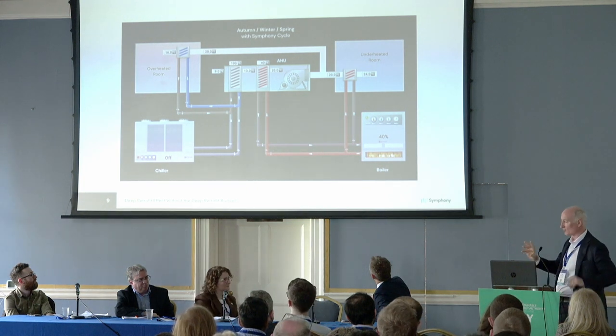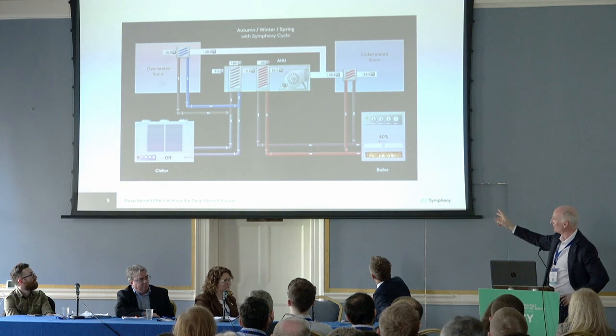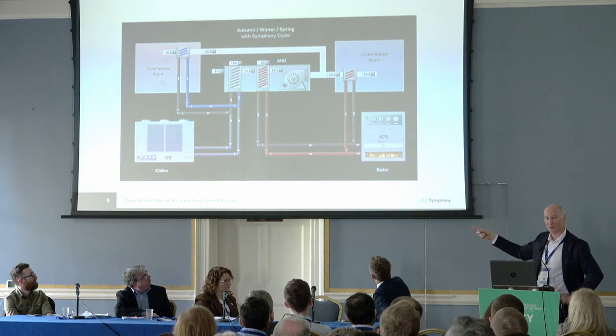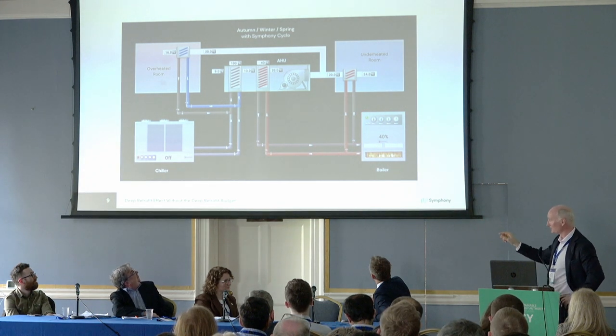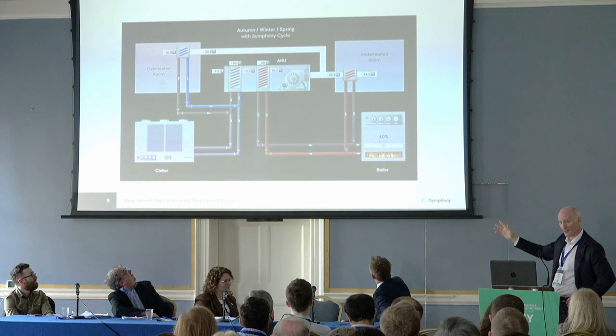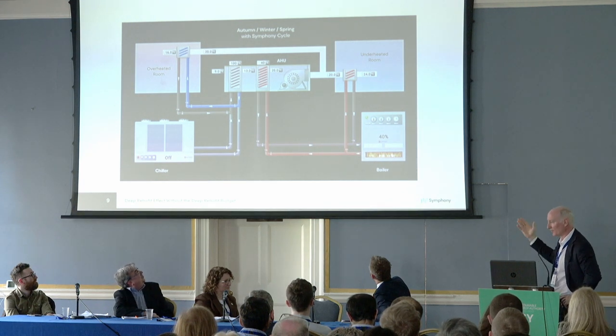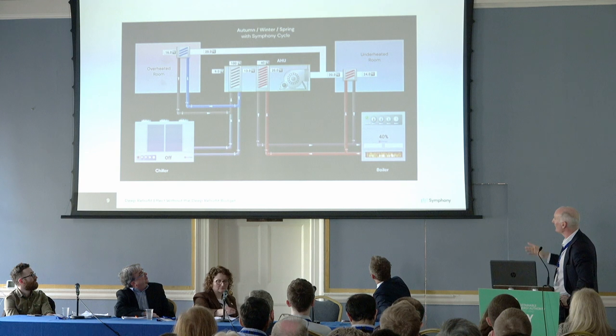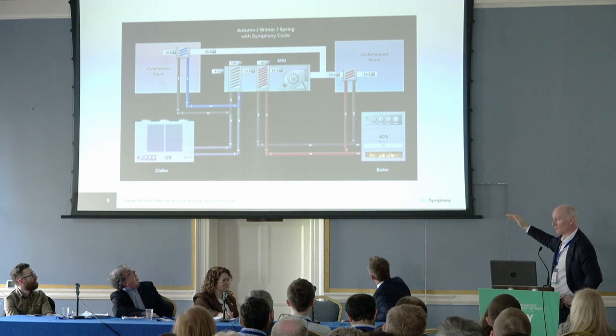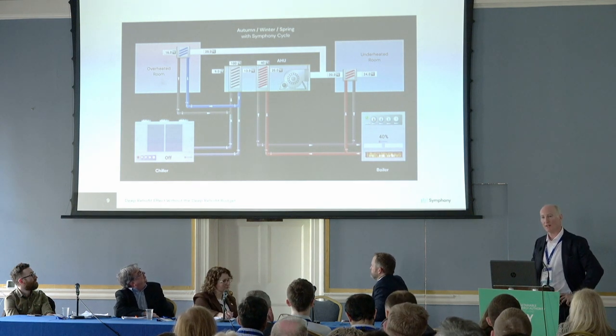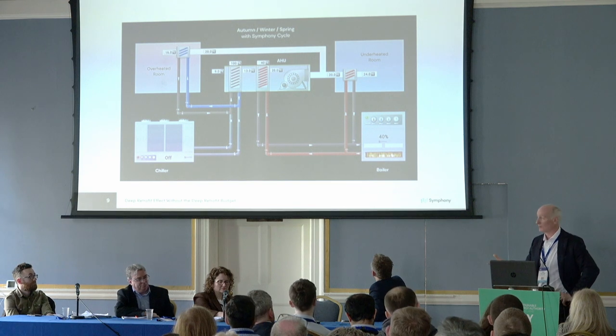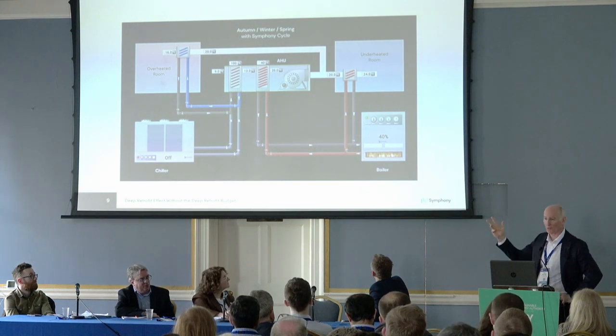Conversely, with that transfer of heat, you're putting it where you want it, it's 100% free heating, which goes into your heating system. Net effect, your chiller's off entirely, and the primary pumping, and if there's condensing pumping as well, that's off, and your boiler is stepped back or off. So it's a phenomenal process. It's got zero input energy because your fan's already operating, your pumps are already operating.